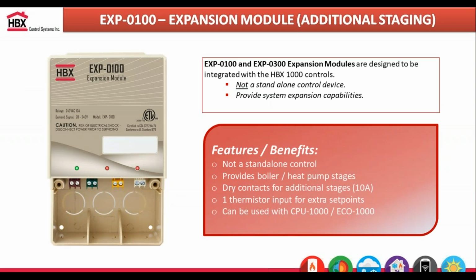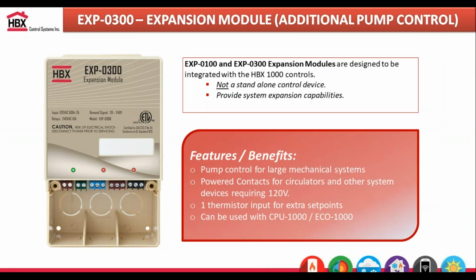So again, the main unit itself can do up to 2 stages. If you wanted to add on more than 2 stages, you would just add on an EXP100, which gives you an additional 2 stages of boiler. You can add a maximum of 6 EXP100s to the CPU1000 for a total of 14 stages. So that's the maximum boiler stages that we can do with the CPU1000. Again, these are just dry contacts, 240 at 10 amps on the 1000 series compared to 5 amps on the 550s, so you get a little bit more pump control with the 1000 series.